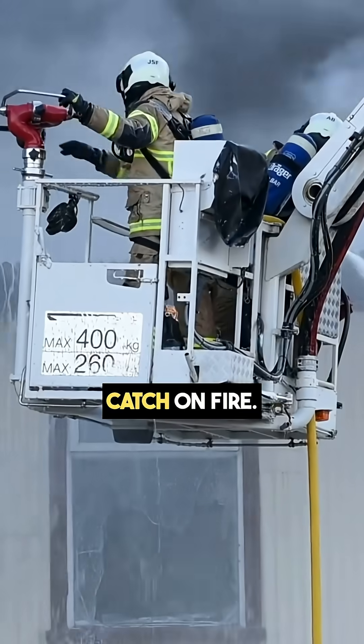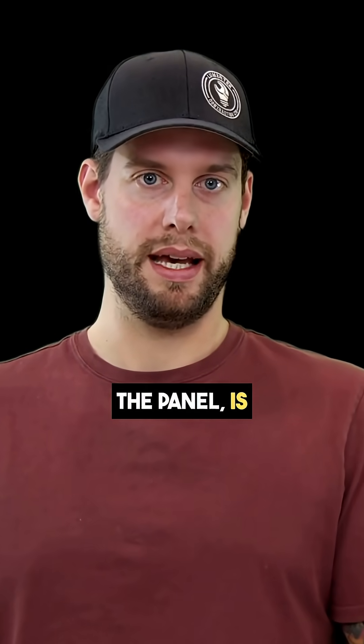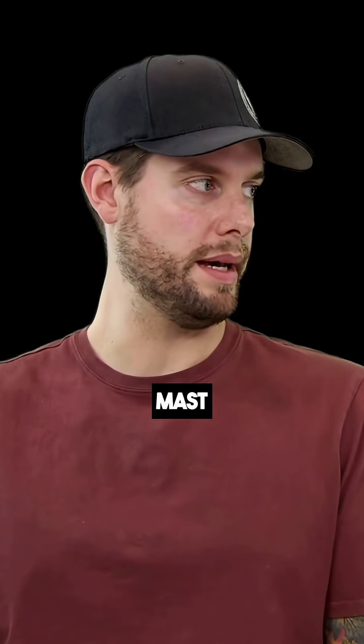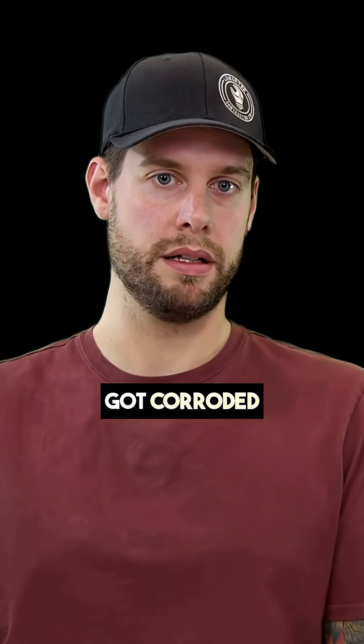Well, he's lucky his house didn't catch on fire. Very lucky. So we looked at it and we're wondering why nothing tripped, why nothing shut off. And I think what happened when we went down to the panel is that the breakers — the way the service mast came in — it could have let water track through that mast into the panel, and the breakers from getting wet over and over got corroded internally.